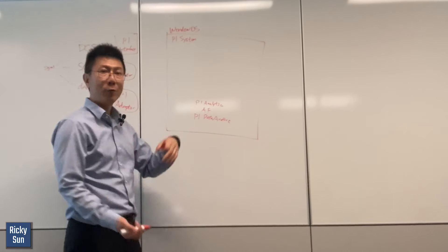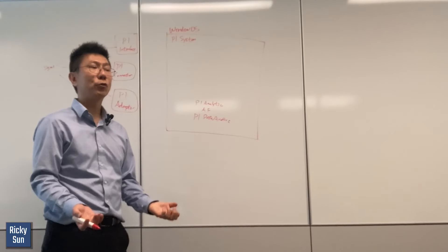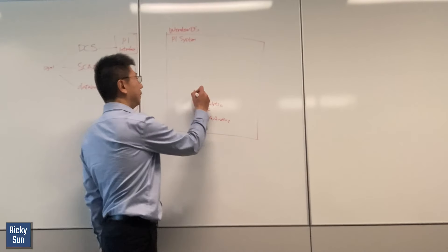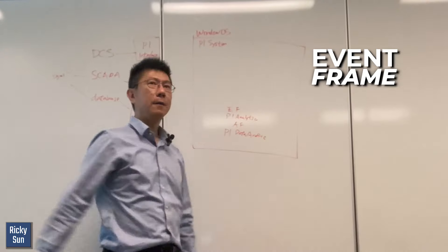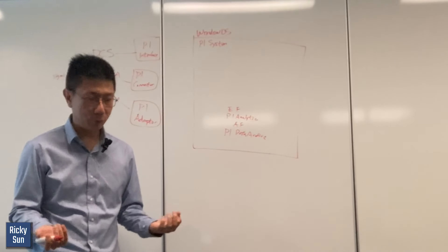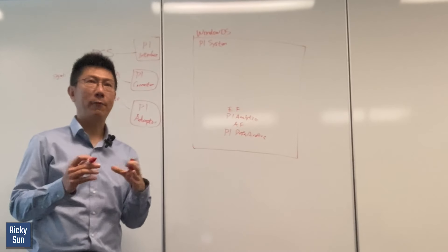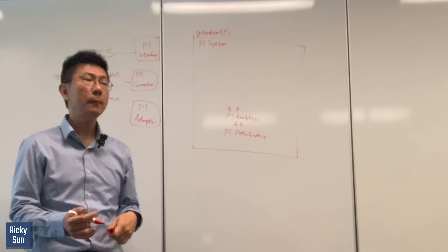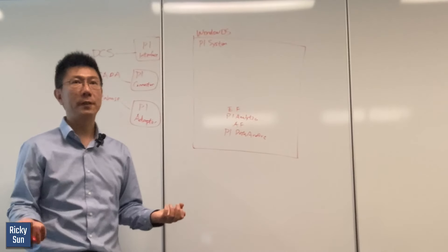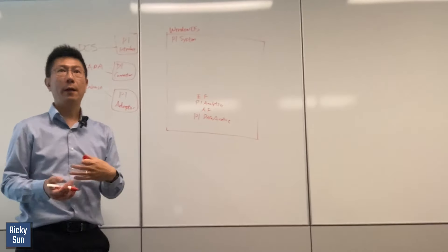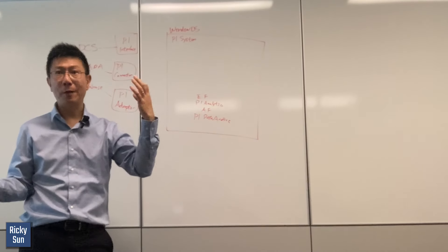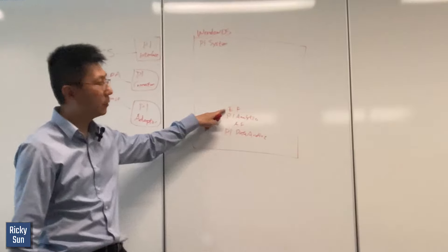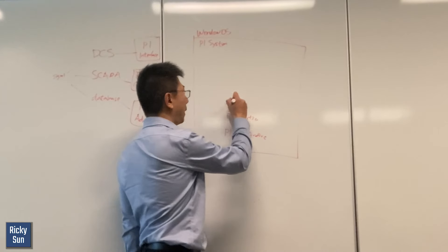Once you create a calculation, you can also create a tag to store the result continuously. On top of that we have event frames. For example, if you have a tank and you don't want the level to go over 80%, you can set an event frame to trigger when it's above 80%. It captures the start time when the level exceeds 80%, and stops the event frame when it drops back below 80%.